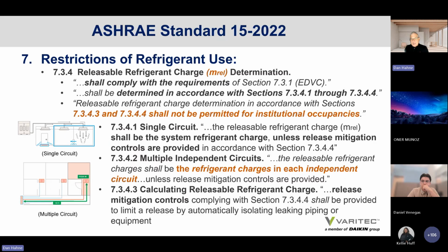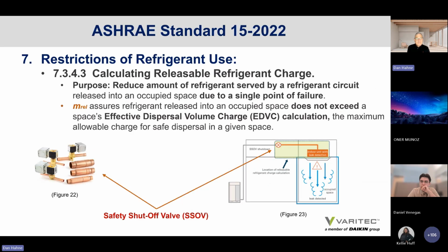The releasable refrigerant charge shall be the system refrigerant charge unless release mitigation controls are provided in accordance with section 7.3.4.4. There's language on multiple independent circuits that defines the releasable refrigerant charge as the refrigerant charge in each independent circuit, unless release mitigation controls are provided. And then there's calculating releasable refrigerant charge with release mitigation controls complying with the standard's section 7 paragraphs listed. So it's a lot of information.